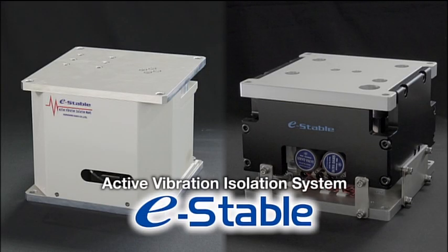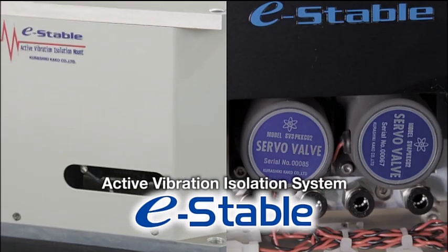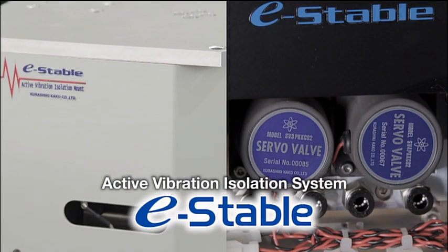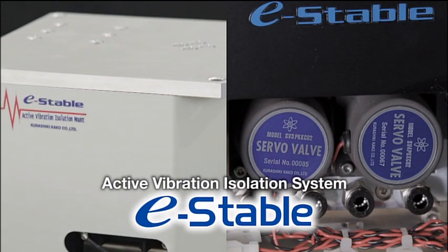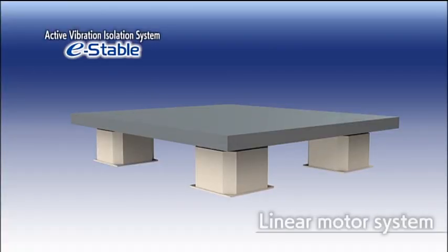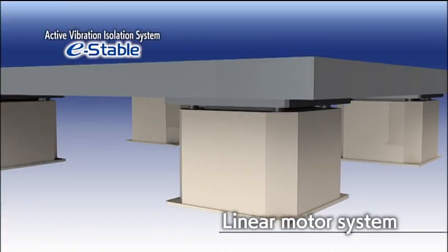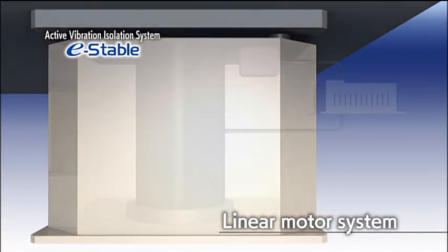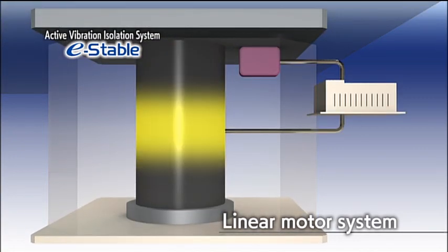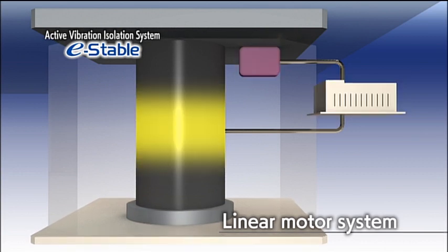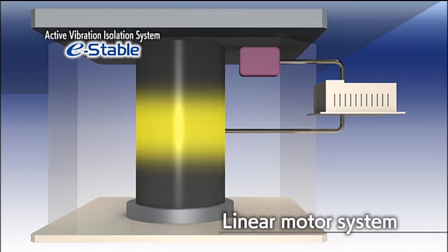Active vibration isolation system: e-stable. The e-stable uses linear motors and servo valves for active operation. Linear motor systems are effective up to the higher frequency ranges and consume very little air. They have excellent vibration isolation and are suitable for equipment requiring high resolution, such as laser microscopes or electron microscopes.